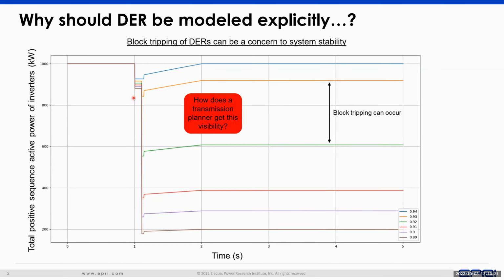Now, DER in such aggregate amounts, if they start tripping - because of how we designed them to trip rather than ride through the fault - that's where the traditional approach runs into trouble in restoring the system.